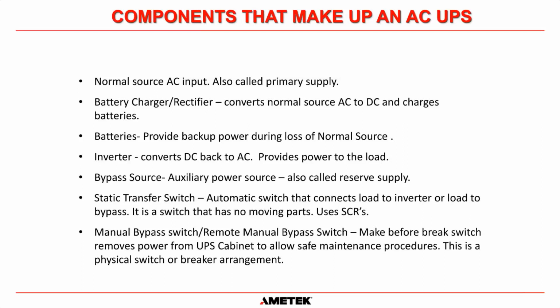And then we also have a bypass source or an auxiliary power source, which can also be called a reserve supply. They are all interchangeable terms, but they mean the exact same thing. It's a backup AC power supply that is not backed up by the battery. That's important to remember. It's usually fed directly from the grid. Sometimes it's fed from a power conditioner, but it does not have any battery backup unless you have a cascaded redundant system, but we won't go into that today.